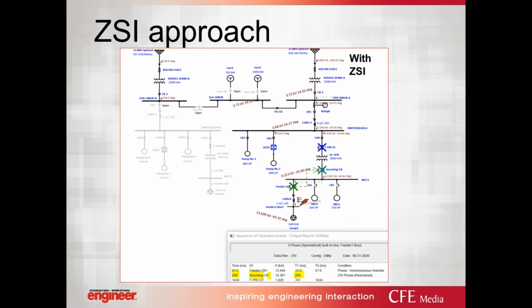That gives us coordination and at the same time reduces the incident energy. Therefore, if you look at this system here, if there is a fault at the load side, the breaker on the load will trip first, then the incoming breaker 250 milliseconds later, and then of course the primary side. ETAP is being utilized for performing this model development on this picture right here.